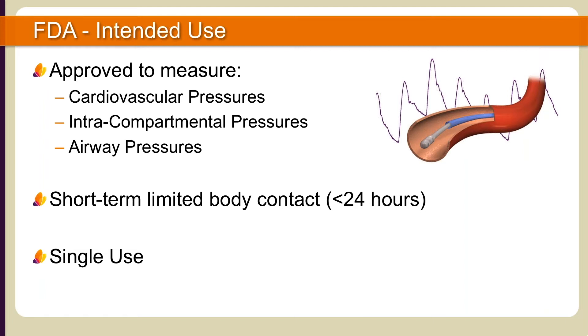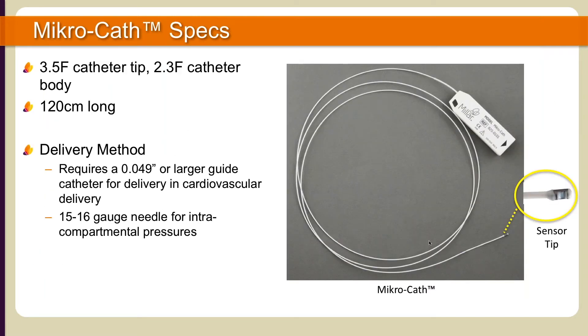It is FDA approved for short-term, less than 24 hours, single use. The Microcath's distal end contains a 3.5-French sensor case containing a side-mounted MEMS sensor. The catheter body is 2.3-French from the sensor case to the strain relief and is 120 centimeters in length. To deliver the Microcath into the cardiovascular system in interventional procedures, the catheter requires support via guide catheter with an inner diameter equal to or greater than 0.049 inches. In most cases, a 5-French multipurpose catheter will work for access into the right or left ventricle. The Microcath can also be delivered through the lumen of a 15- to 16-gauge needle to measure intracompartmental tissue pressures.